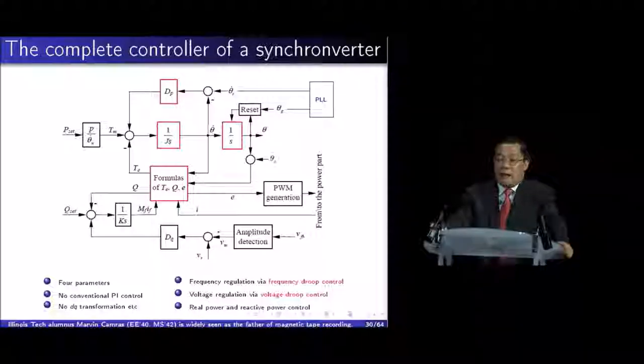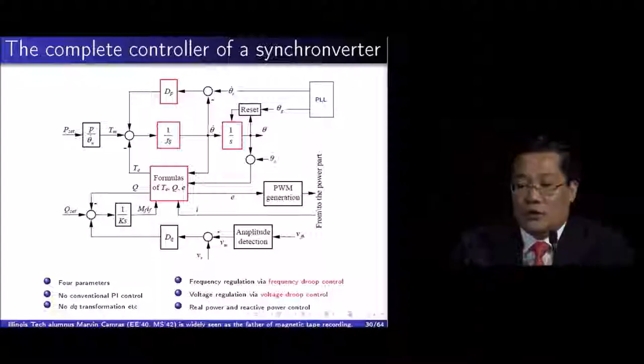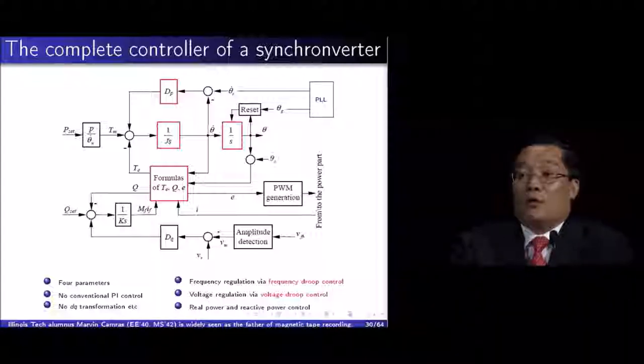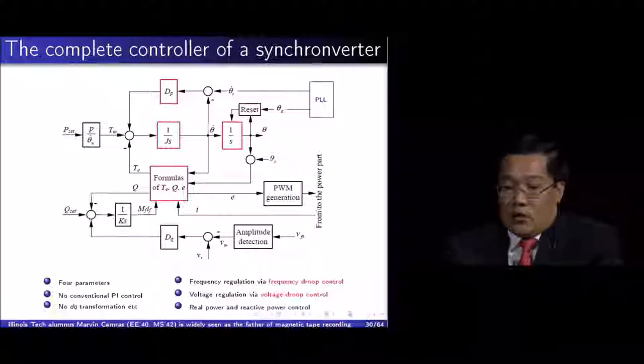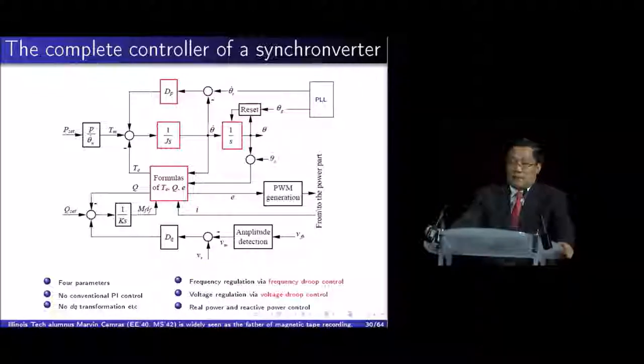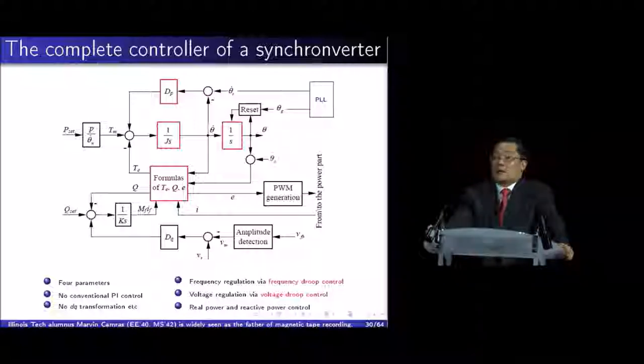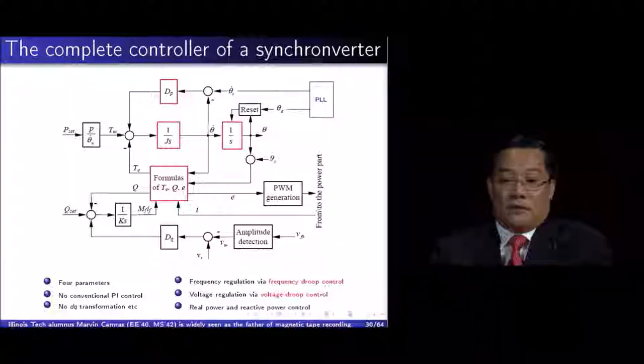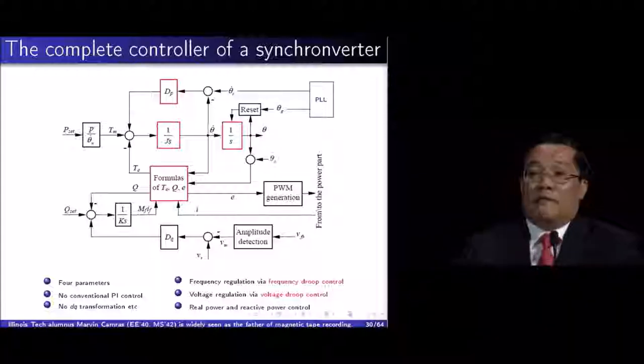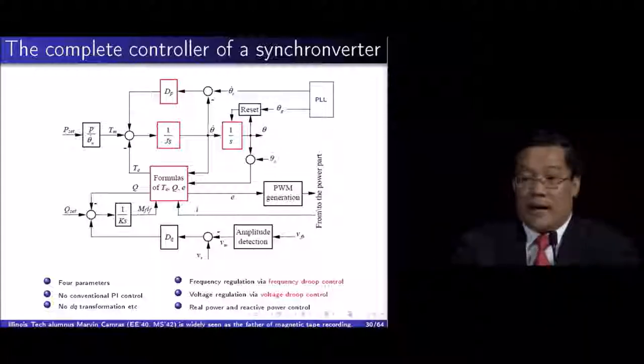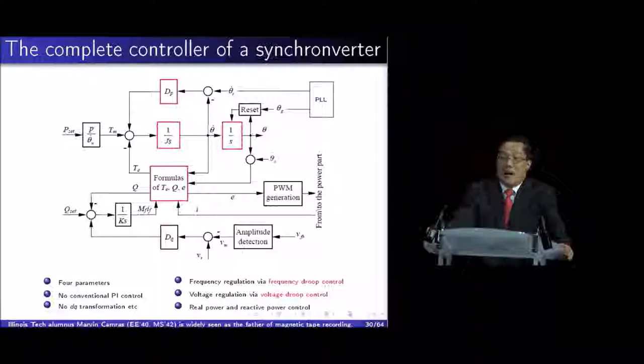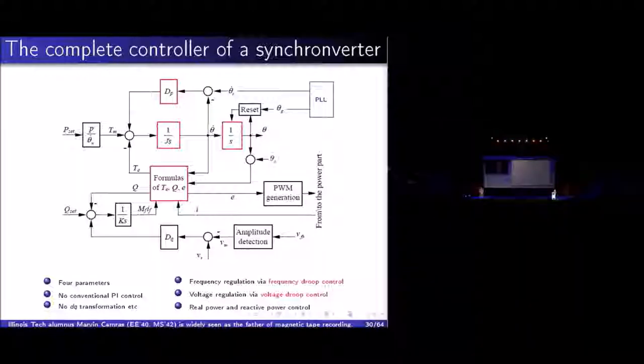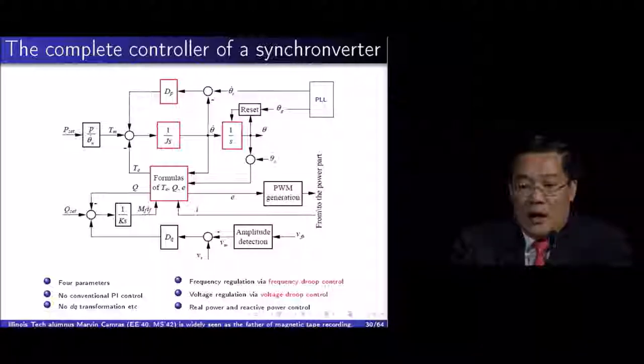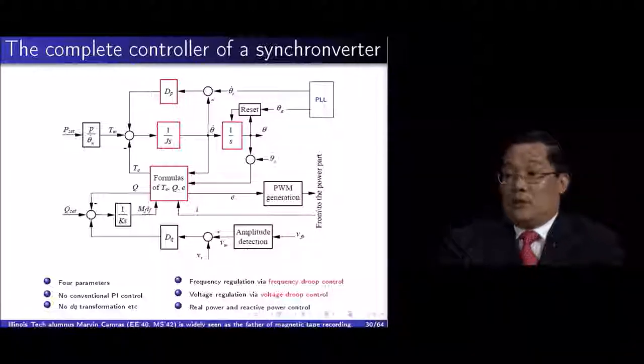...is to add a summation block on the top right to compare the frequency of the synchronverter, theta dot, with the reference frequency. We found that the virtual frequency coefficient Dp has the role of frequency droop control. We added a block to convert the real power into mechanical torque Tm to regulate the real power, and then added an integrator to regulate the field excitation current MfIf, so that we are able to regulate the reactive power.